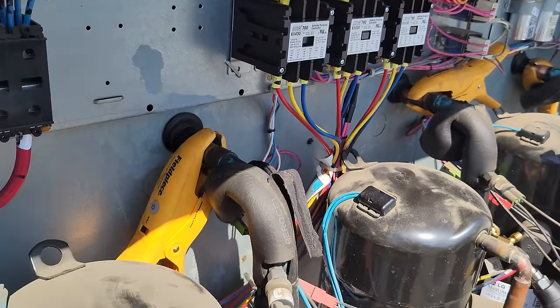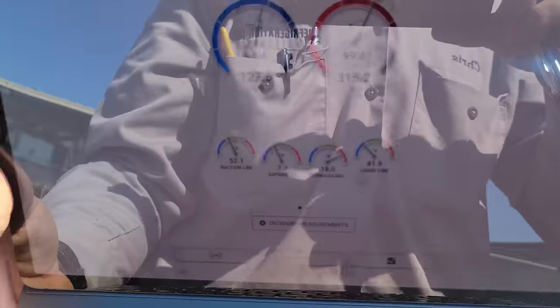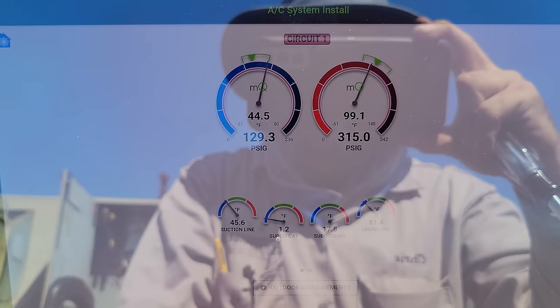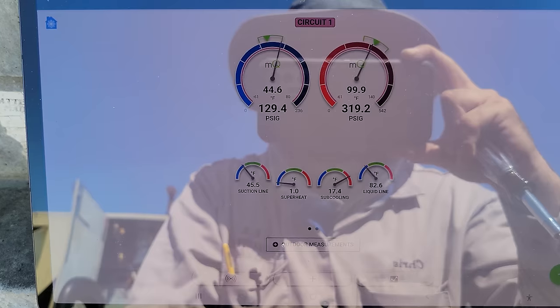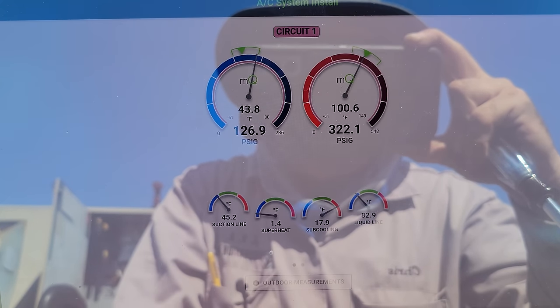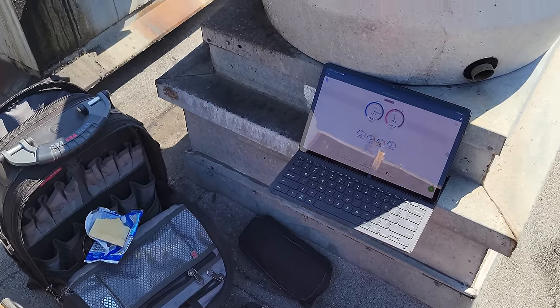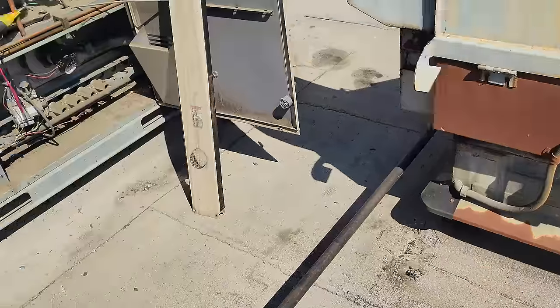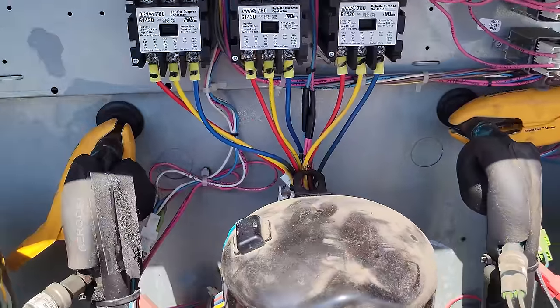That's just the first stage — second stage hasn't come on yet. That's really bizarre. I'm going to let it run for a little bit, monitor it, and check the temperature drop across the dryer. This unit is blowing my mind. Third stage — it's like it's not running. I come over here to measure voltage because the compressor is red hot but the contactor is pulled in. Look down here — the wires arced out!